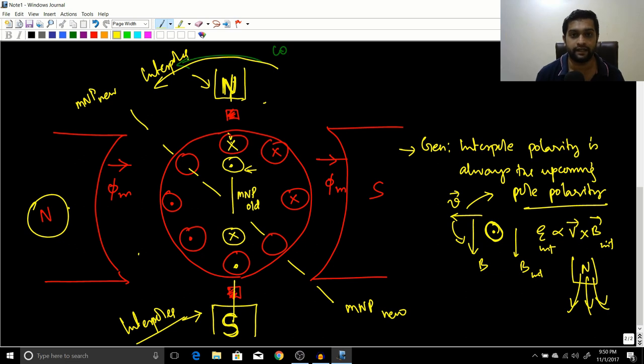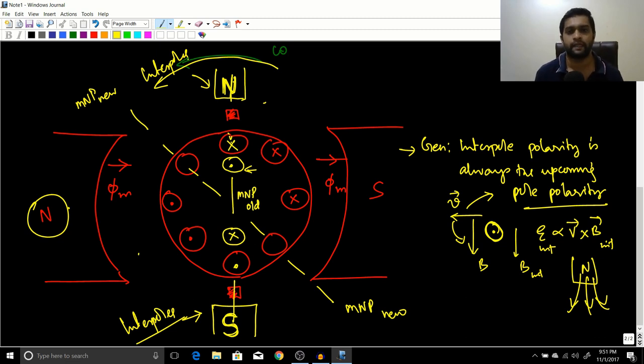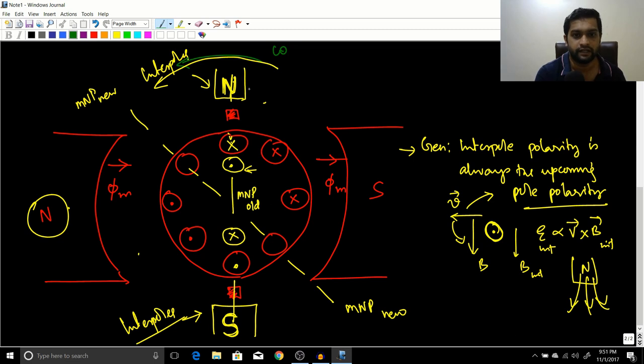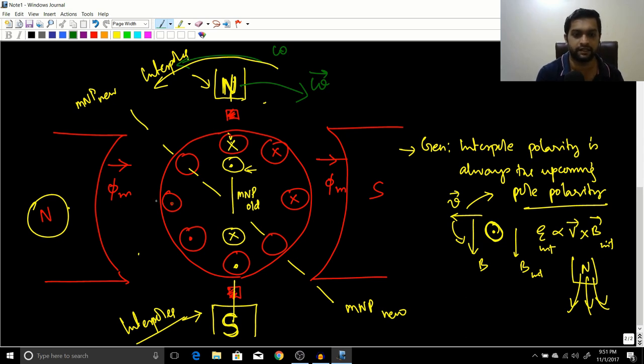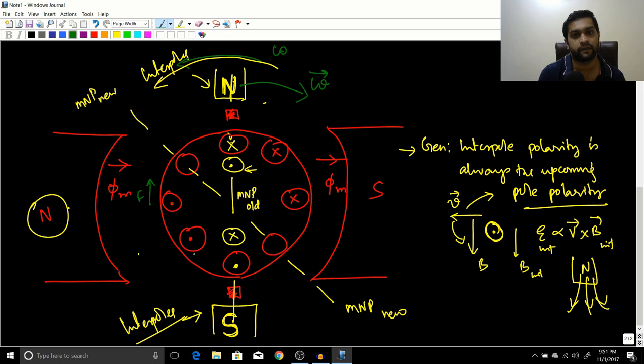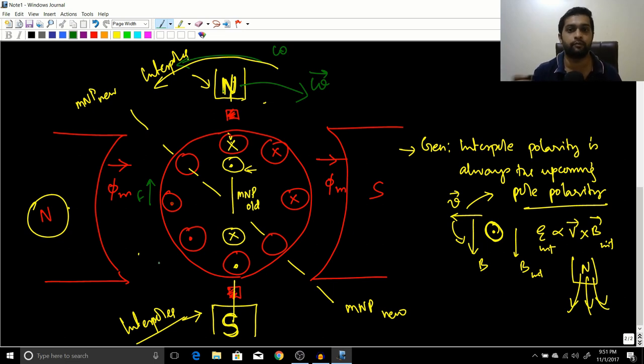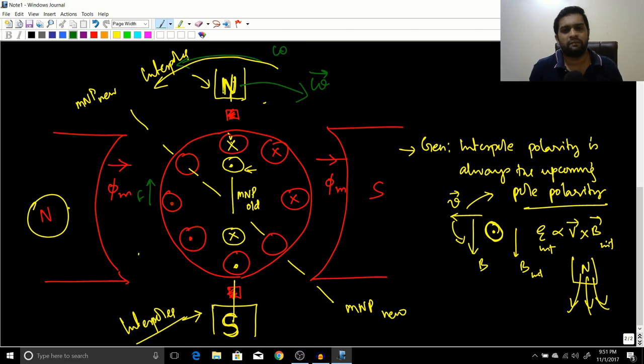For a generator, the interpole polarity is always the upcoming pole. For a motor, the interpole polarity is always the previous pole. This is because when the same machine is connected as a motor with the same current configuration, the direction of rotation becomes clockwise, and correspondingly the interpole polarity must match the previous pole to achieve the same cancellation effect.